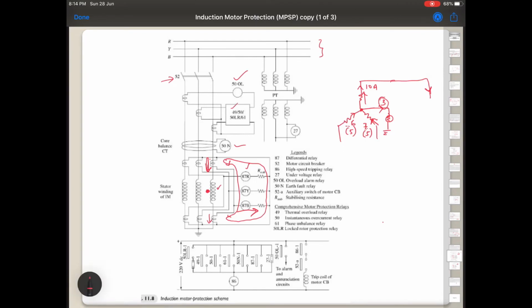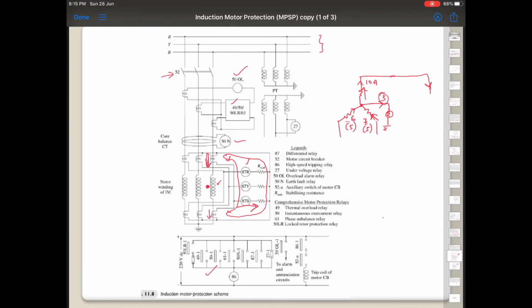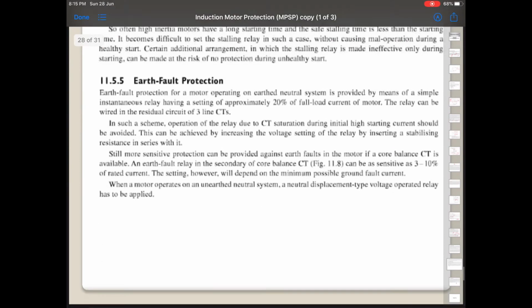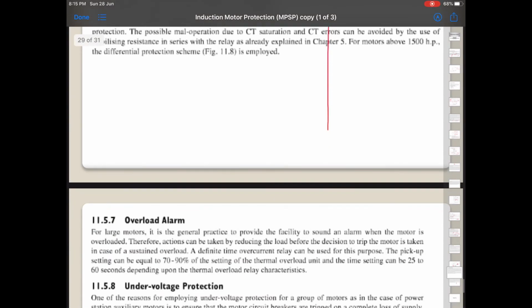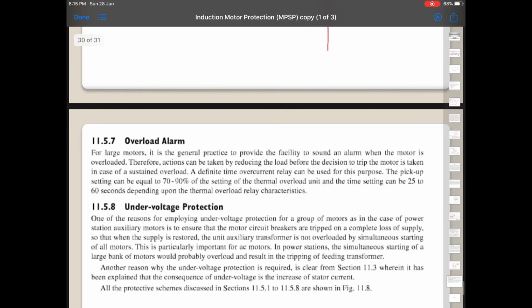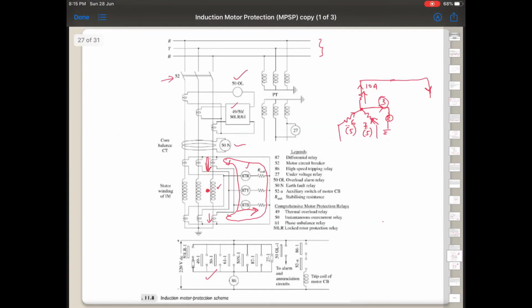And we have a thermal overload relay here, an instantaneous relay, a phase unbalance relay, and many different types of relays implemented here. Since most of the concepts are explained through this diagram, the next few concepts like earth fault protection, differential protection, overload alarm, and under voltage protection have already been explained. I hope those are simple, you can go through them on your own. So this is the end of the induction motor protection. Thank you.